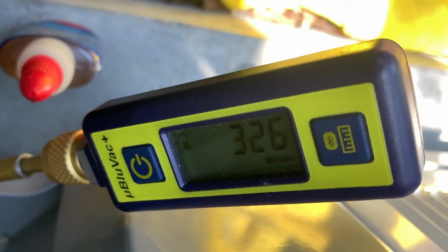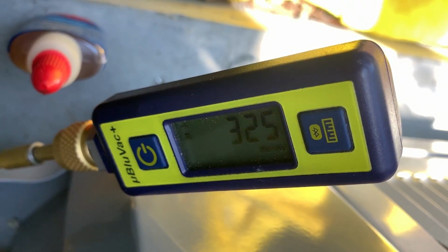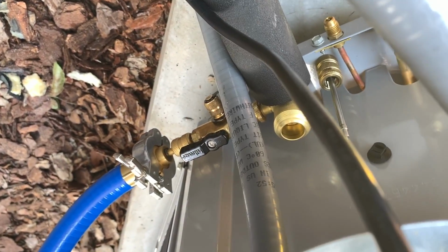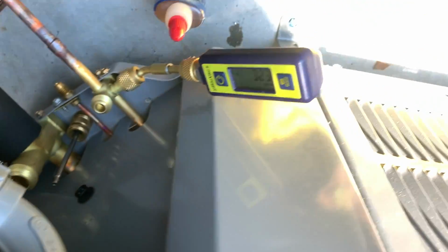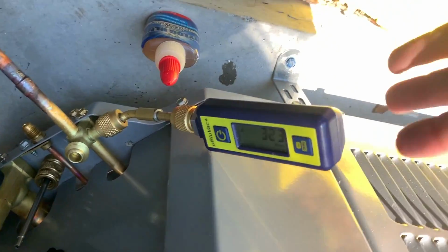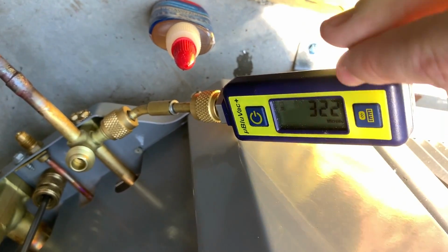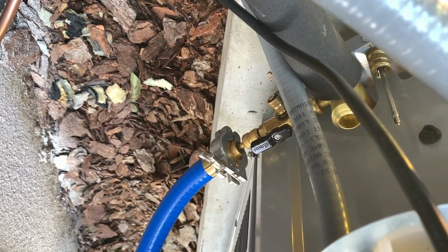Some microns. So we're going to let it run a little longer, do our isolation test, where we shut it off at the valve, make sure that it doesn't rise beyond the acceptable decay limit, which on this generally our rule is you pull it below 500, you know, in the 300 range, valve it off. If it doesn't rise above 500 in 10 minutes, you're good to go.